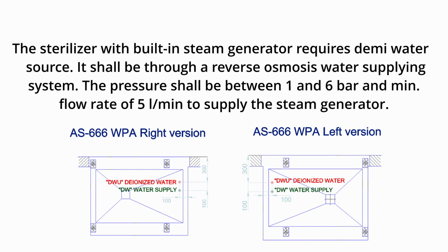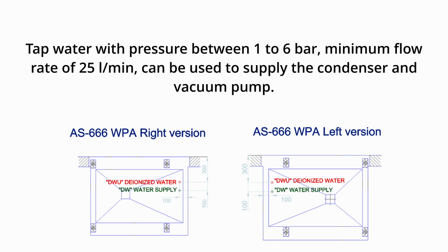The sterilizer with built-in steam generator requires a demi-water source. It shall be through a reverse osmosis water supplying system, with a pressure between 1 and 6 bars and minimum flow rate of 5 liters per minute to supply the steam generator. Tap water with a pressure between 1 to 6 bars, minimum flow rate of 25 liters per minute can be used to supply the condenser and vacuum pump.